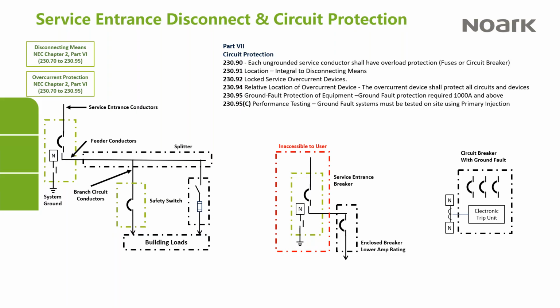Where a service disconnect is inaccessible to the end user, it requires a second disconnect device to be included in the system. So if this service entrance breaker had to be mounted inside a locked room that the end user couldn't access, then the code requires a second disconnect device to be mounted downstream of it, and it must have a lower amp rating so that this one trips before the service device would trip. Okay.